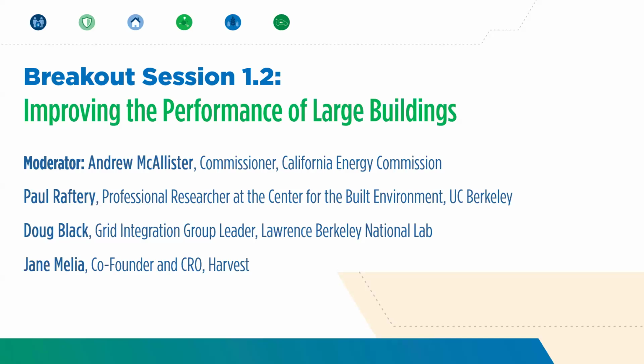Tying it back to the slides I presented before, one of the ways building owners can get relatively immediate emissions reductions is through efficiency measures. It's a hugely underestimated element of a decarbonization plan. Most people are familiar with retro commissioning projects that save on the order of 5 or 10%. That's not what we're talking about here. We're talking about in-depth controls efficiency measures that save 50% of HVAC. Because you're saving energy rather than shifting from gas to electricity, they come with utility cost savings. Even though there's a small cost upfront, they have relatively short paybacks you can leverage to do other things later, while getting those emissions reductions upfront.